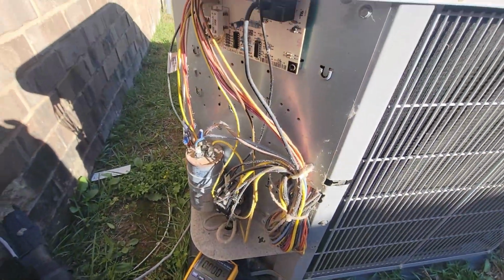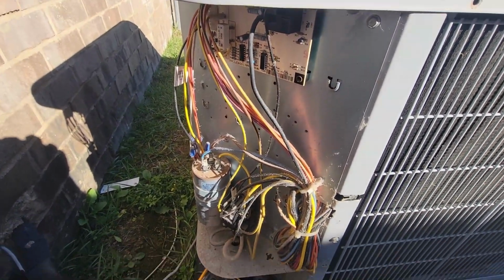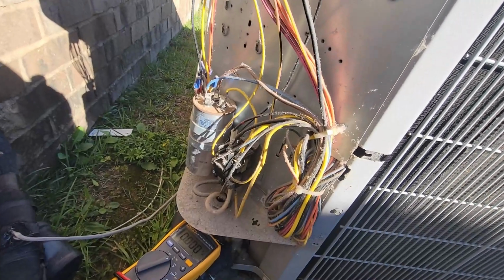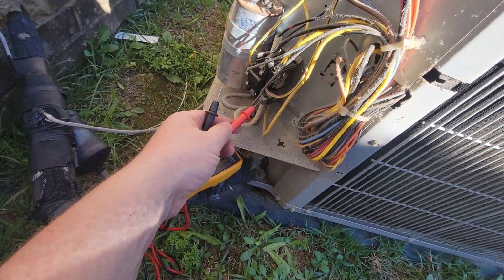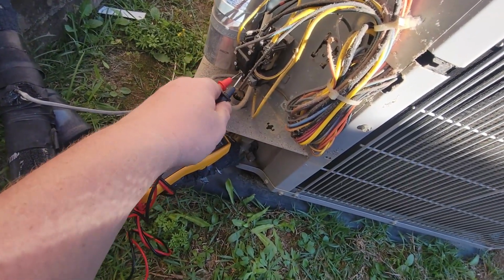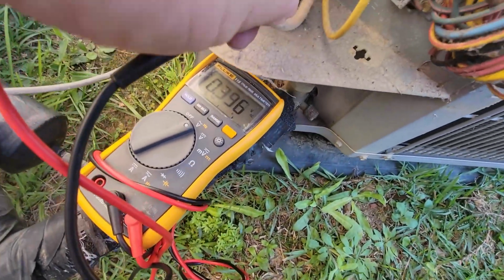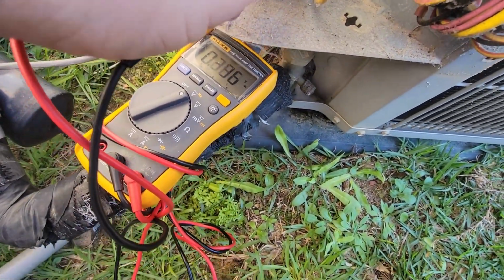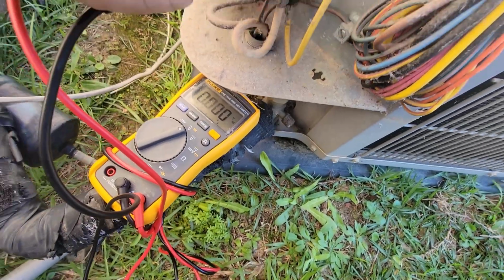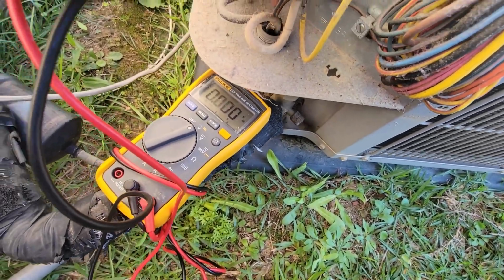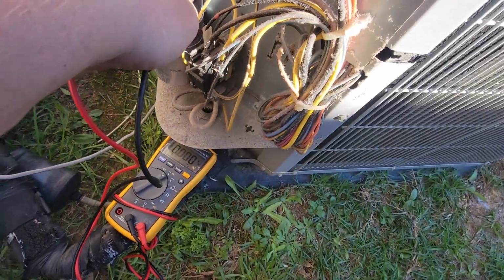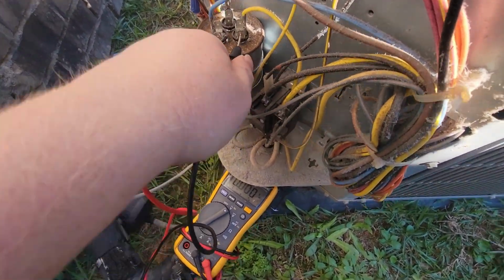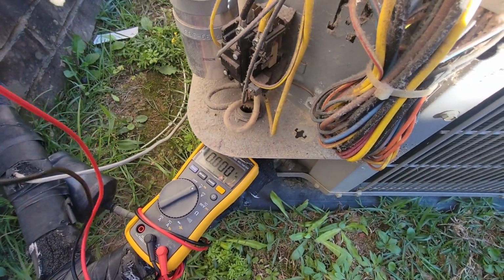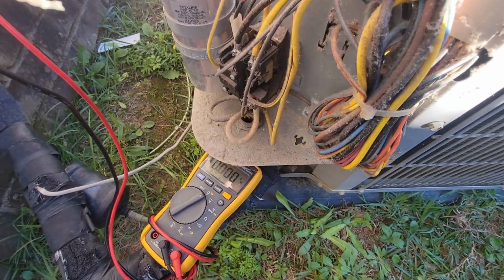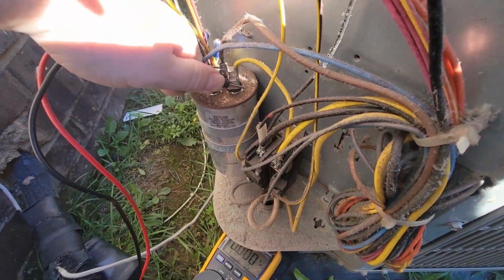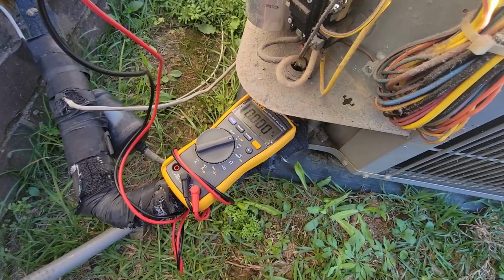And with the AC removed from the circuit breaker, the first thing I'm going to do is come in here and remove this side panel. And using my multimeter, I'm going to come across the line right here and just make sure that we do not have AC coming in. We see it's fully killed. I can check the other side. I shouldn't have anything there either, which is good. Also, just come through and briefly touch the contacts on top of this dual capacitors in here, just making sure that nothing's stored on the cap.